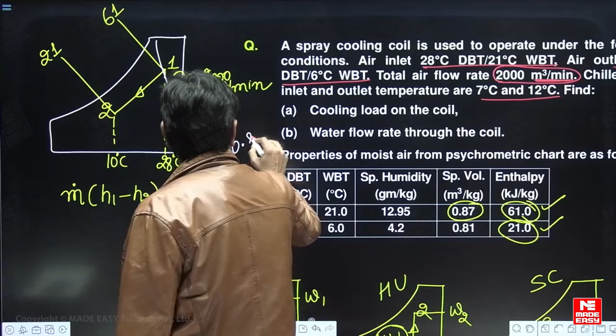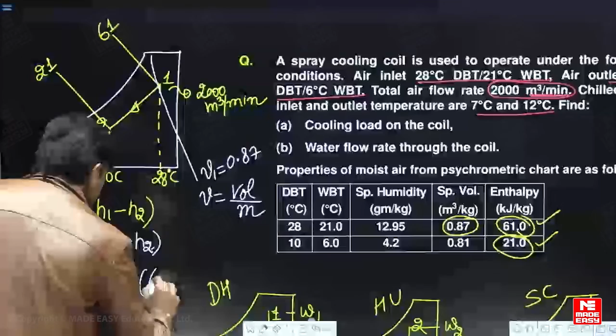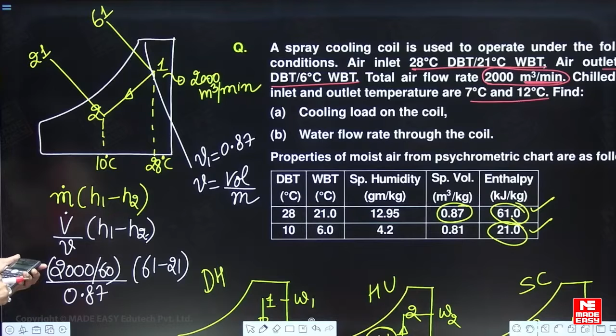So what is the value of volume flow rate? 2000 meter cube per minute. I will convert into seconds, and the specific volume is 0.87, and this is 61 minus 21. So 61 minus 21 into 2000 divided by 60 divided by 0.87.